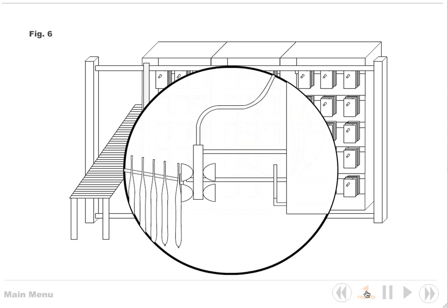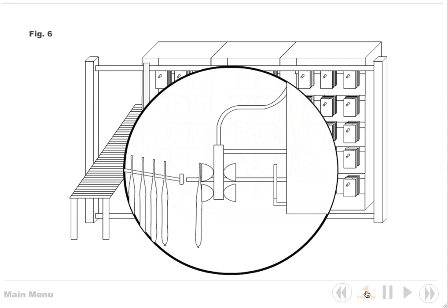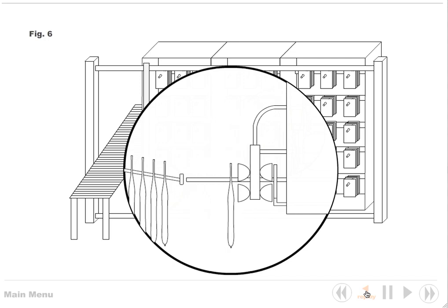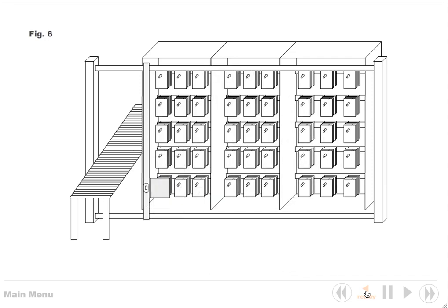After contacting the medicine package, the picking means moves backwards so that it may retrieve the package from the storage rod of the storage rack and place the package on the storing rod of the picking means. The vacuum suction created is sufficient to hold the package so that it can be transferred from the storage rod of the storage rack to the storing rod of the picking means.